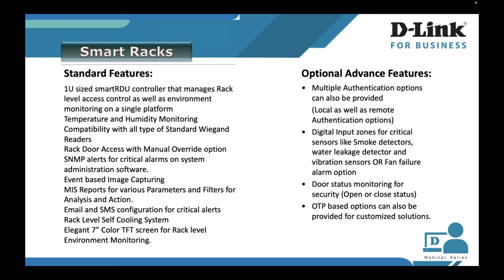With smart rack's remote triggering and log management, you may have a person on-site but you don't have dependency on them. You can always review logs, always get triggers when something goes wrong, call that person to take care of it, or go there yourself. Features include temperature and humidity monitoring with all types of Wiegand readers, rack door access with manual override option, SNMP alerts for critical alarms, and a hooter that raises an alarm to draw the attention of on-site personnel even if they've stepped away.